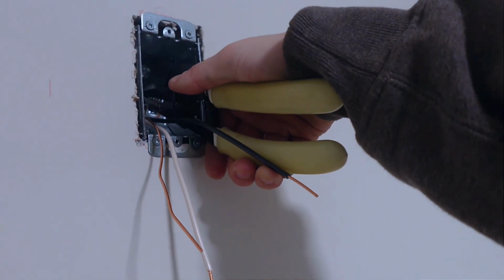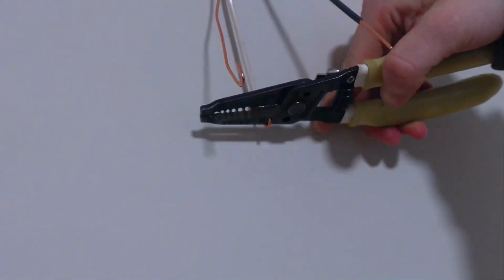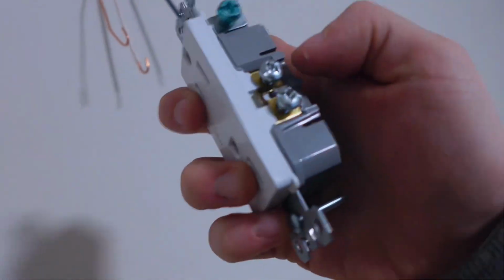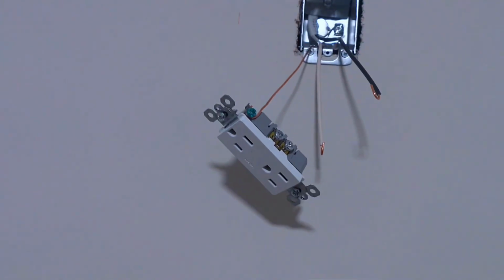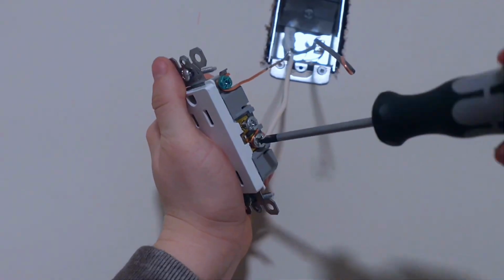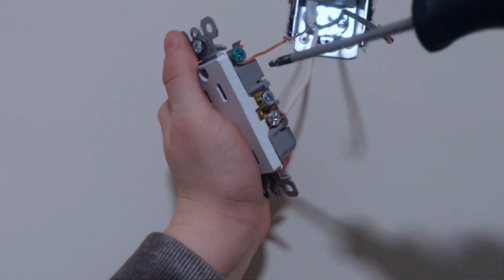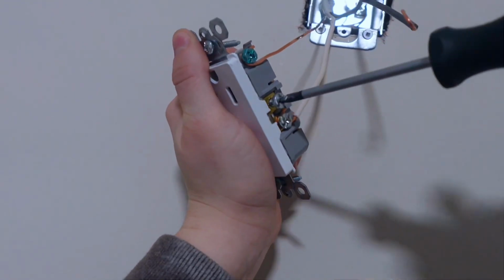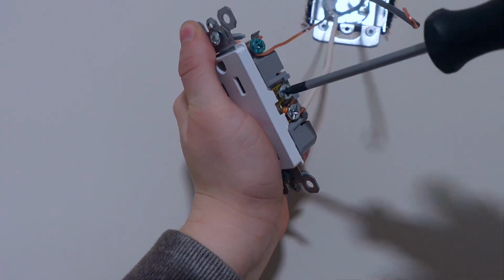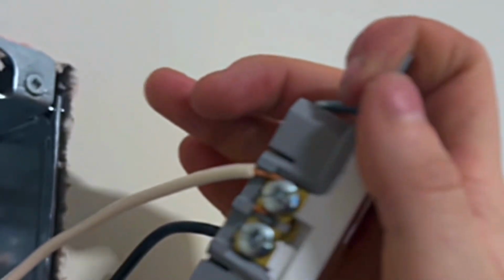I usually do a stripper's length from the back of the box. Now we are going to be using the little hole in our strippers to curl all of the wires. These will be wrapping around the screws of the receptacle in the direction that the screw tightens. Tighten it just snug. And then we also want to screw in our extra screws that aren't being used. Like I said, it's just common practice. It doesn't change the way that these receptacles work, but it's nice to get them out of the way.